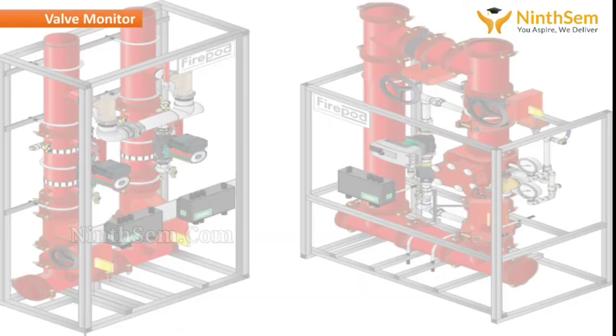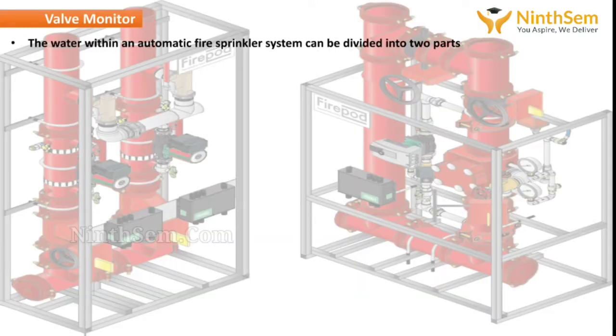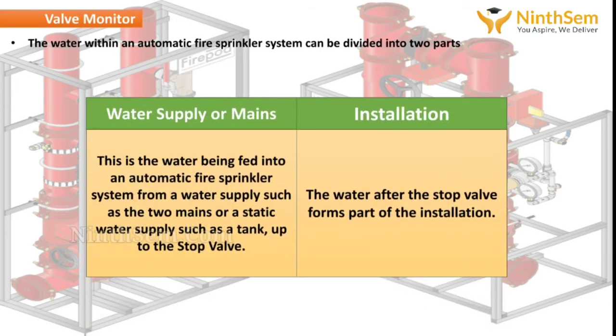The water within an automatic fire sprinkler system can be divided into two parts: water supply or mains, which is the water being fed into an automatic fire sprinkler system from a water supply such as the town mains, or a static water supply such as a tank, up to the stop valve. And the next one is installation. The water after the stop valve forms part of the installation.